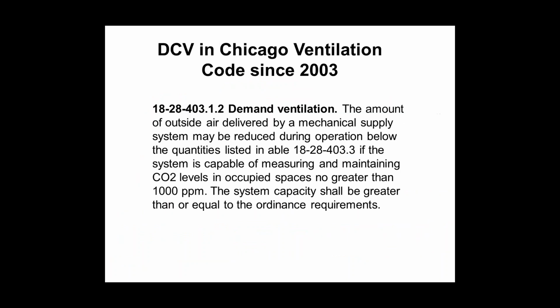The City of Chicago, in regards to CO2, is actually ahead of the curve, and they came out with language in their mechanical code to allow CO2 a year before the rest of the country did. The City of Chicago does it a little bit differently, though. Instead of letting you, as an engineer, decide what the set point should be, they give you a fixed set point of 1,000 parts per million that you cannot go above in the space.